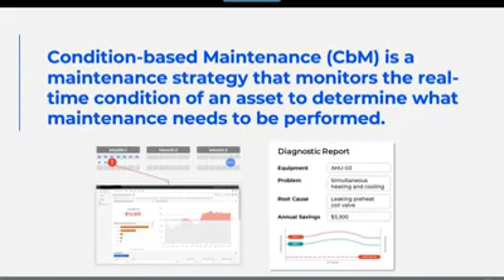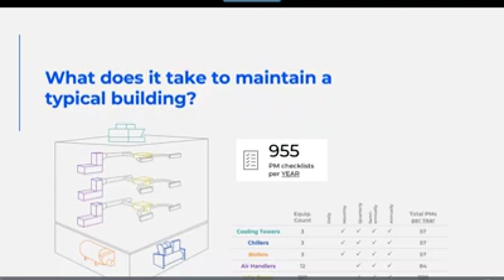In reality, what this looks like is a shift and an increase in the number of checks we can do and the frequency. A typical scheduled PM service contract will have a number of checks - say we're doing 1,000 checks throughout the building over the course of a year. What FDD technology enables is more checks. We have all these fancy algorithms looking at more pieces of data, trying to identify more issues in a facility, and we're doing this every single day.